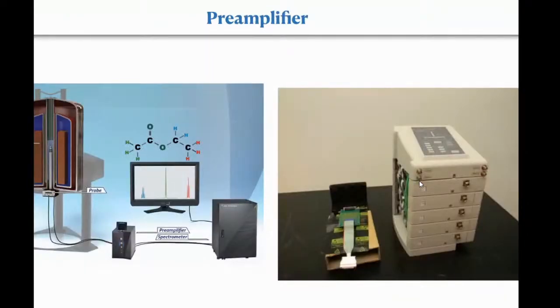Right, so as I told you, you have this probe which is connected to a preamplifier, which is then connected to an NMR console, which is then connected to the computer and screen. So this is a JEOL setup, okay? This is a Bruker preamplifier which I found outside.